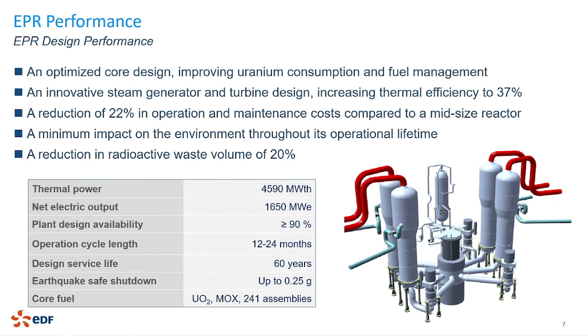The other feature is that you have 4 steam generators, which are well-proven U-tube heat exchangers, but equipped with an economizer flow design which improves the heat exchange between the primary and secondary side of the system, and increases the pressure compared to standard steam generators with the same surface area for heat exchange. Combined with a pretty efficient turbine, this gets you to a thermal efficiency of 37, even 38% - so it's a highly efficient nuclear reactor.